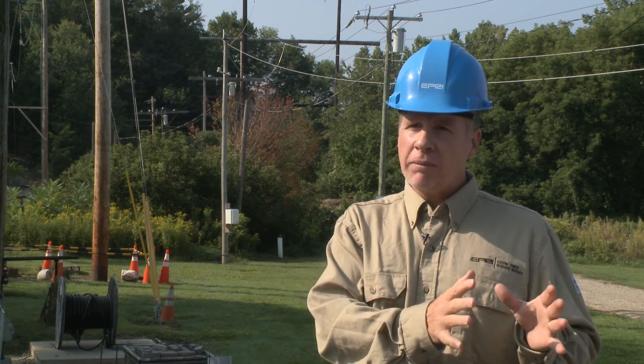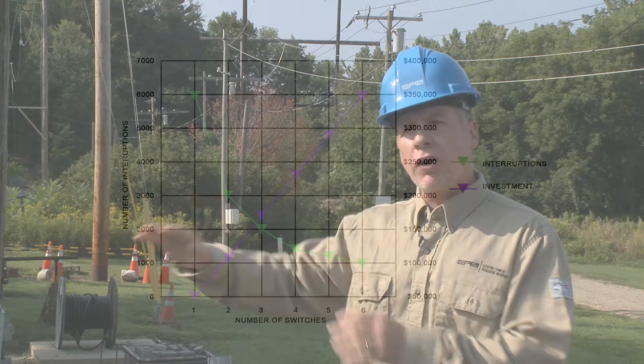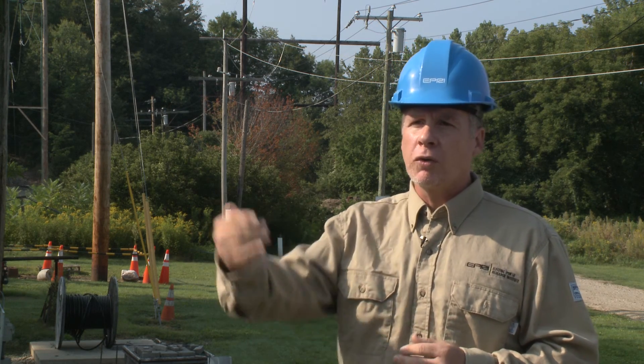The software now enables two processes: one is determining where the switch should be located, but secondly, it also allows the utility to look at each circuit and figure out how many switches should be deployed using the reliability benefits and the investments required. We repeat that iterative process to locate the second switch, then the third. We can calculate the dollar investment per reliability benefit, and at some point those benefits level off — a point of diminishing returns — which clearly shows where the utility should stop deploying.